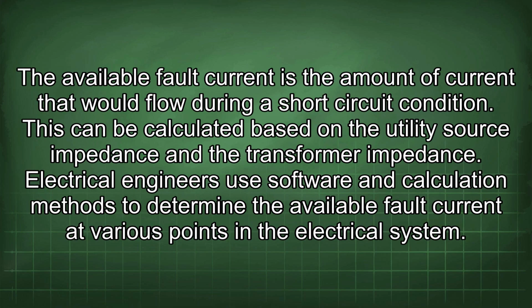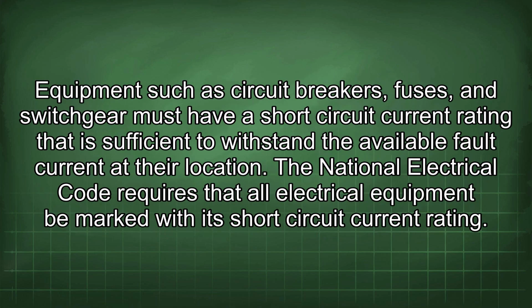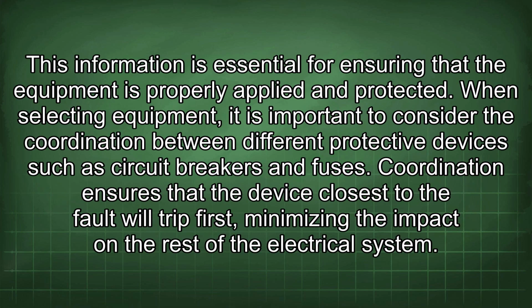The available fault current is the amount of current that would flow during a short-circuit condition. This can be calculated based on the utility source impedance and the transformer impedance. Electrical engineers use software and calculation methods to determine the available fault current at various points in the electrical system. Equipment such as circuit breakers, fuses, and switchgear must have a short-circuit current rating that is sufficient to withstand the available fault current at their location. The National Electrical Code requires that all electrical equipment be marked with its short-circuit current rating. This information is essential for ensuring that the equipment is properly applied and protected.